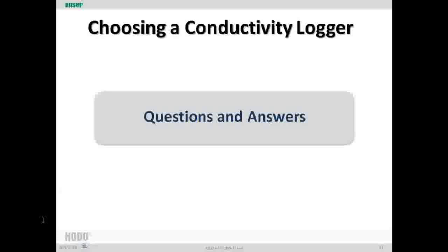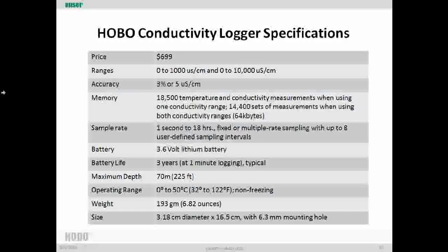Yeah. Actually, in case anybody was interested in a little bit more details on the HOBO conductivity logger, I have a slide here. Let me see if I can go to it. There it is. Sorry about that. If you look at, there's a couple of ranges. There's two ranges on the HOBO conductivity logger. One's up to 1,000 microsiemens per centimeter, and one's up to 10,000 microsiemens per centimeter.